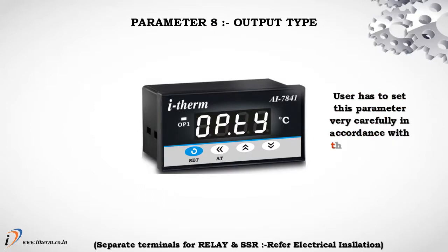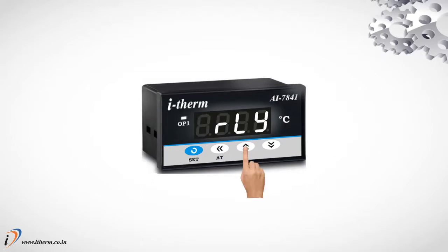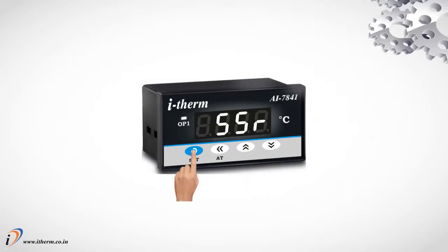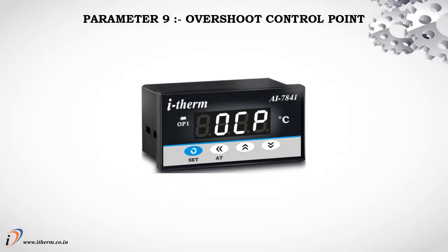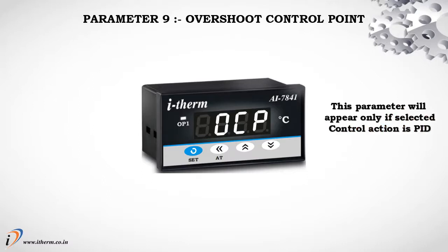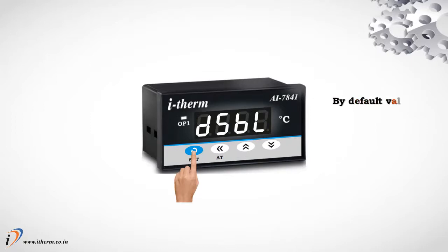User has to set this parameter very carefully in accordance with the output used. Select relay if load is connected via contactor. Select SSR if load is connected via SSR. Parameter 9, Overshoot control point. This parameter will appear only if selected control action is PID. By default, value of overshoot control point is disable.